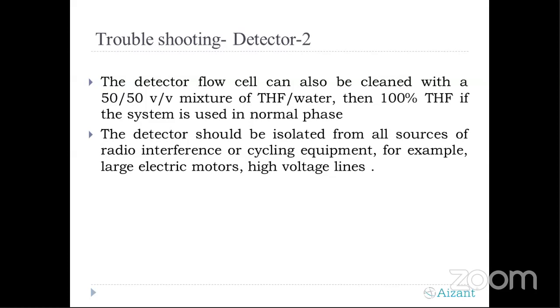Now the last point is very surprising: we have to isolate our detector from cyclic equipment or electronic motors and high voltage. This is a practical challenge which we faced in one of the labs. We brought 4 or 5 new HPLCs, established them, and there were a lot of challenges during qualification of this equipment. We called the vendors, and they thought our instrument was okay, but once we started the calibration, there were a lot of problems. Then the investigation was extended to the engineering department, and we found that behind the wall of the analytical lab, huge high voltage lines were kept. Because of the high voltage and high currents passing through, the magnetic field they were creating was giving challenges to this instrument.